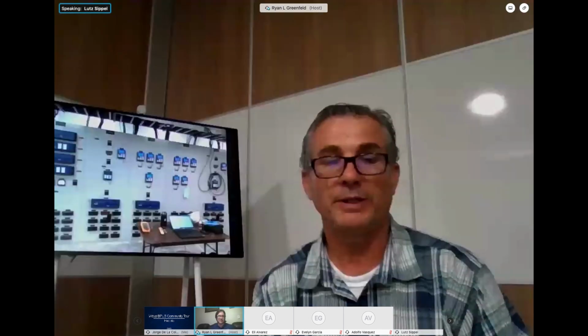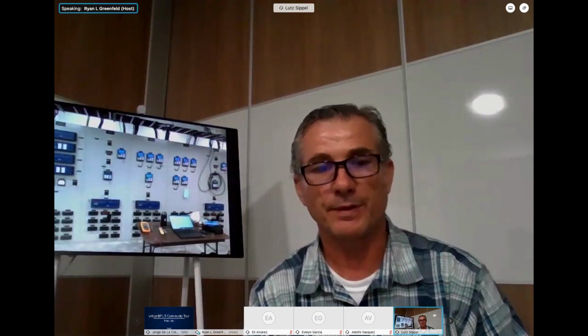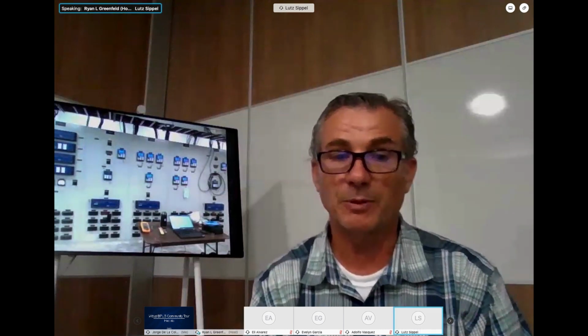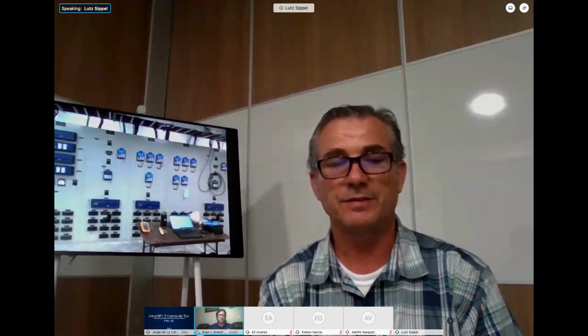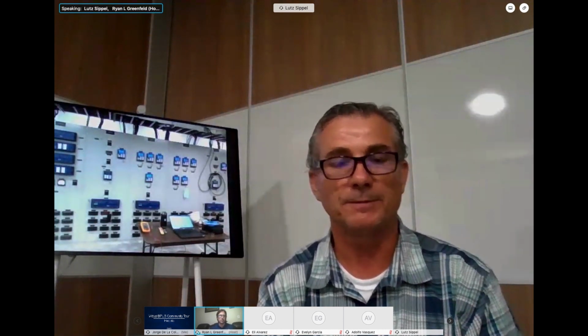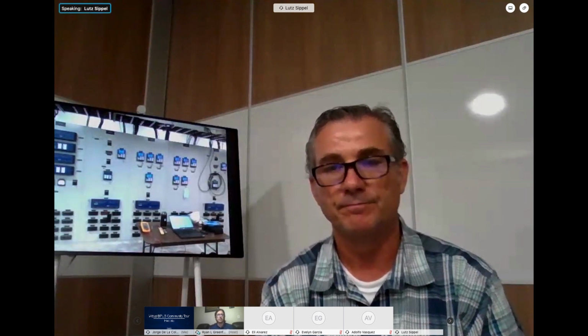And the substation we were just in, at the time of that interview, wasn't energized yet, but it is now, isn't it? Yes, we energized it shortly after that. Both transformers are online, and the distribution feeders are already doing their work. Unfortunately we've had a couple of trips, but they reclosed immediately, so that tells us the system is working just as intended. We're quite happy with that.